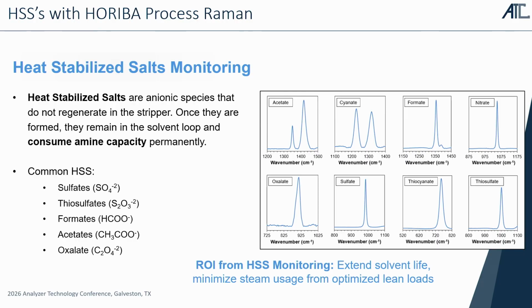So a really important point that a lot of our customers talk to us about is this idea of heat-stabilized salt monitoring. So heat-stabilized salts are just anionic species that do not regenerate in the stripper. So once they are formed, they remain in that amine solvent loop forever until that amine gets taken out and then the new one gets brought in. And so over here on the right side of the slide are different fingerprints of Raman signals of very common heat-stabilized salts, such as oxalates, cyanates, thiocyanates, sulfates, all of those problematic salts. And by being able to directly measure these heat-stabilized salts down to double-digit, single-digit ppm levels, this is helping extend the solvent life and minimize steam usage from optimized lean loads. So instead of just running your stripper and your steam over and over and over again, your solvent might already be done because of these heat-stabilized salts being too high anyways.